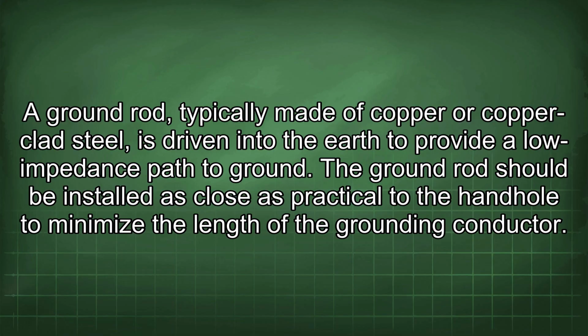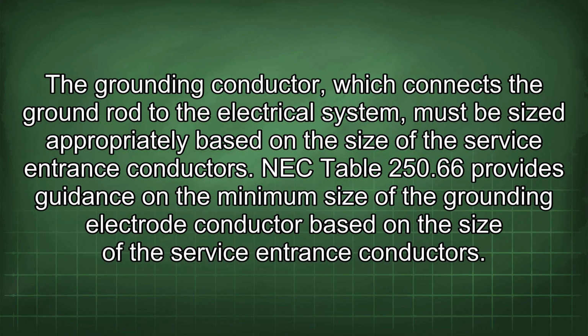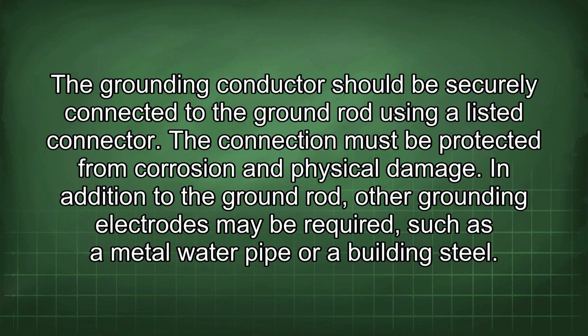the grounding conductor. The grounding conductor, which connects the ground rod to the electrical system, must be sized appropriately based on the size of the service entrance conductors. NEC Table 250.66 provides guidance on the minimum size of the grounding electrode conductor based on the size of the service entrance conductors. The grounding conductor should be securely connected to the ground rod using a listed connector. The connection must be protected from corrosion and physical damage.